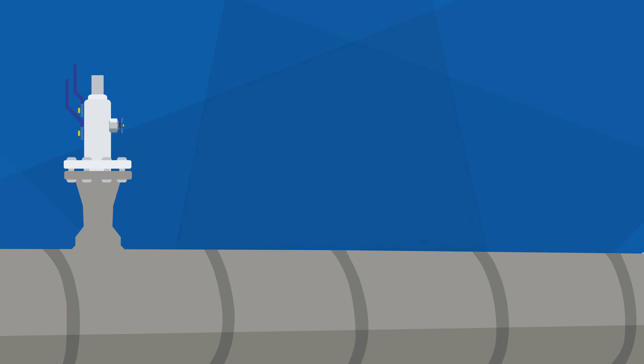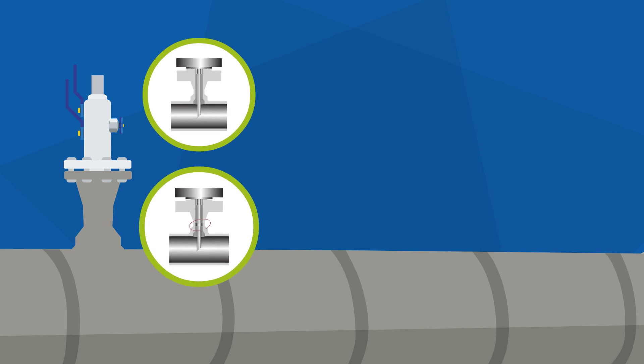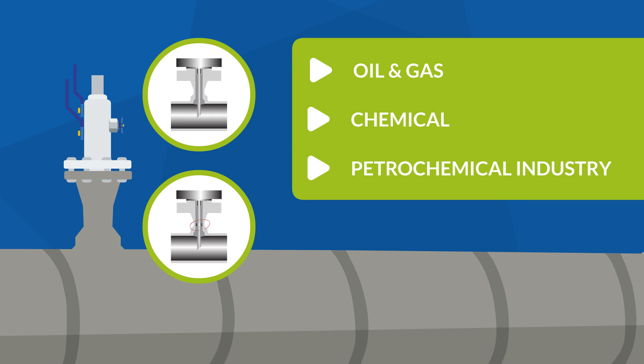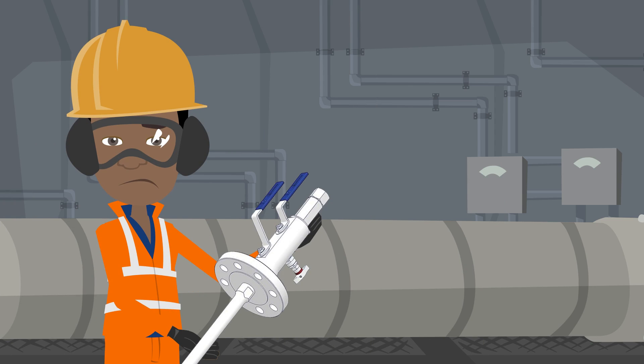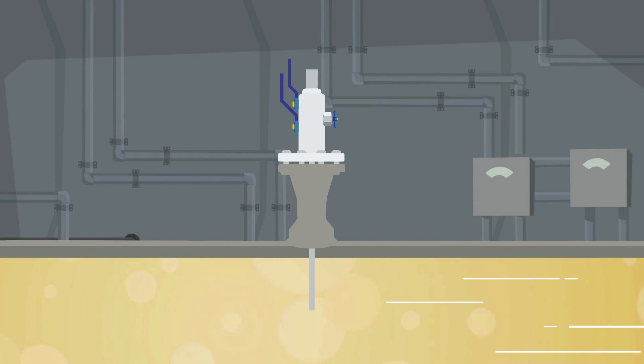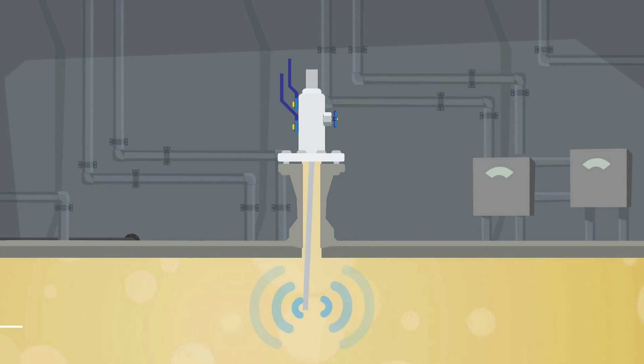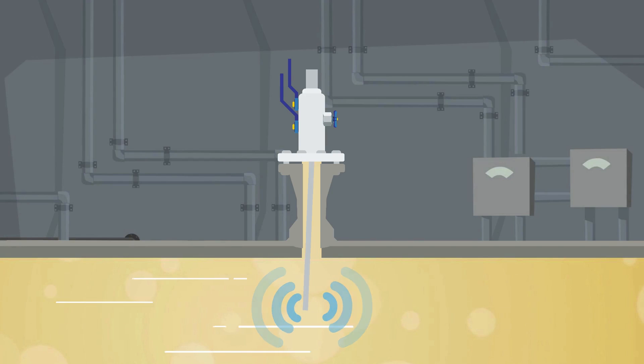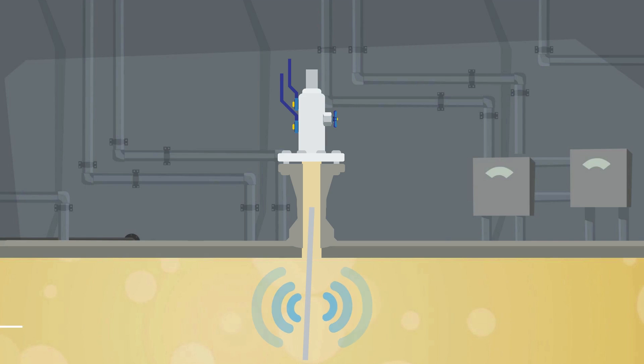The use of injection or sampling DBB valves with or without a support collar is a common application in the process industry, like oil and gas, chemical, or petrochemical industry. But injection or sampling applications can also be very tricky, because an object inserted into a pipeline can prove disastrous if it is not properly designed. In the case of a sampling or injection probe, the vibration generated by the flow can cause the probe to vibrate so strongly that it breaks.